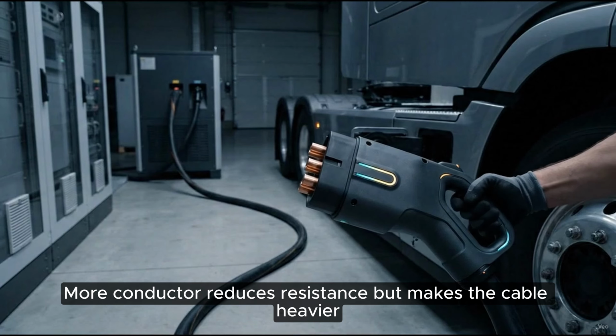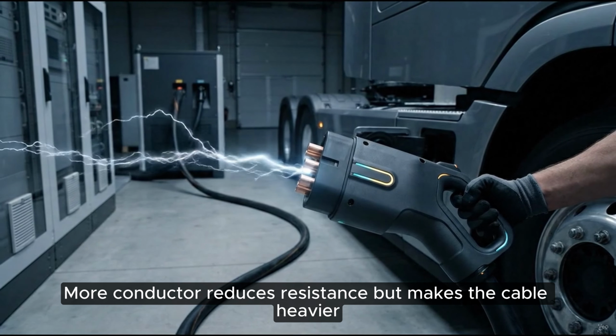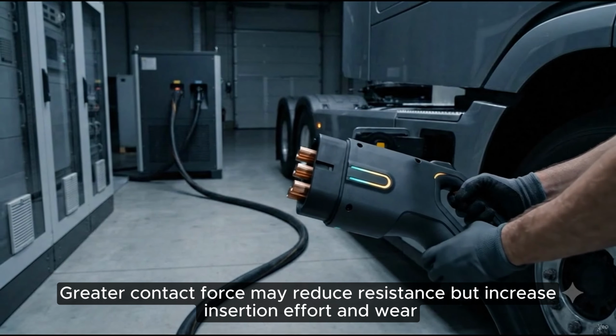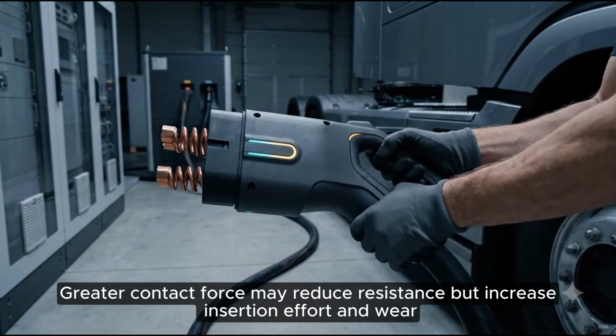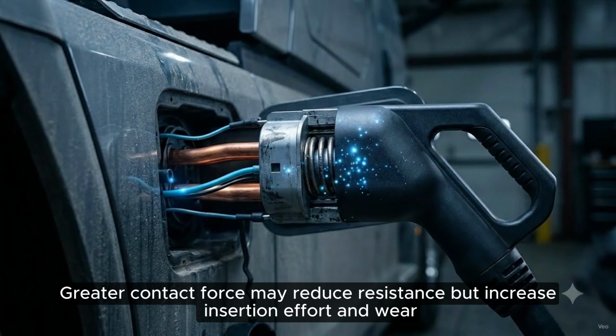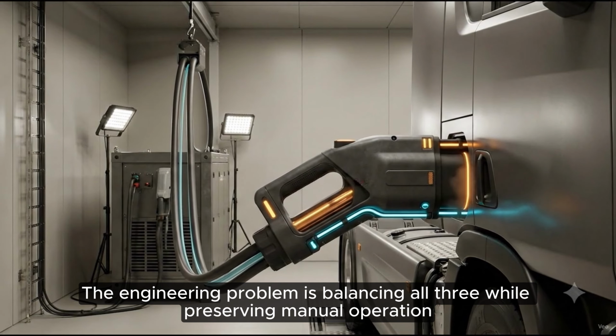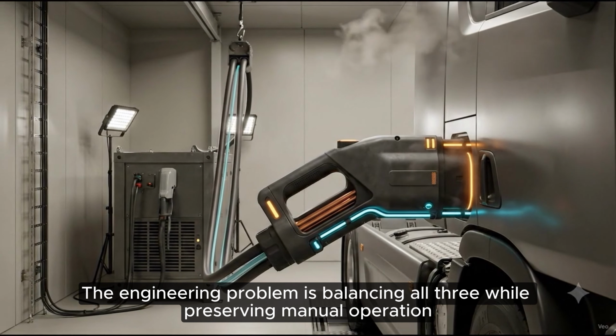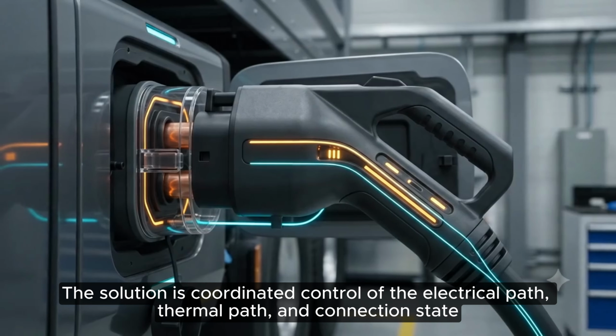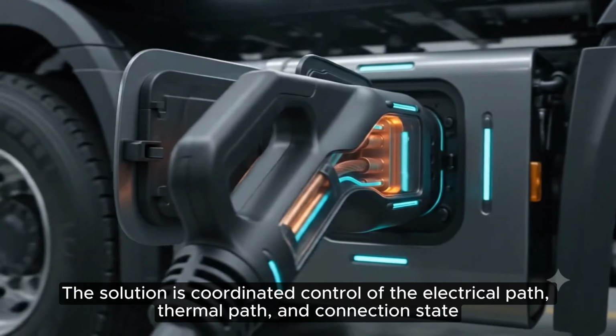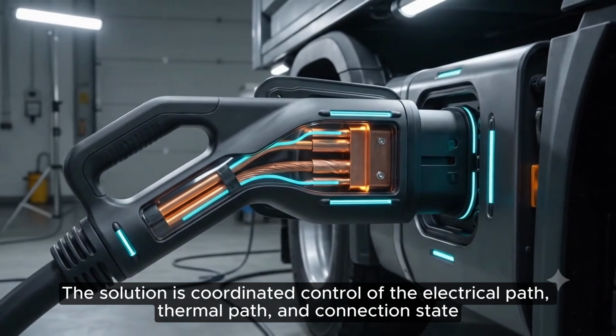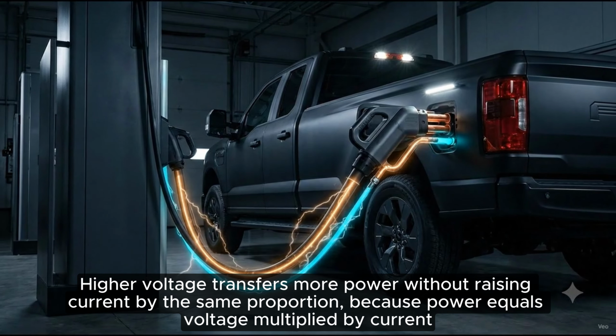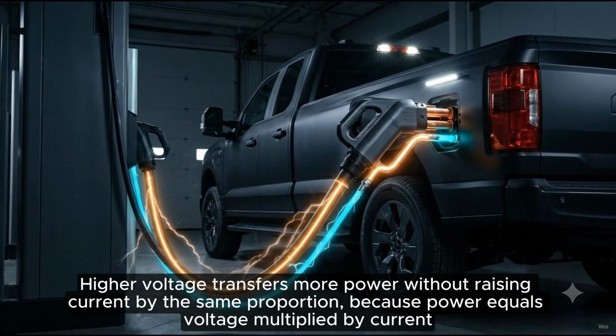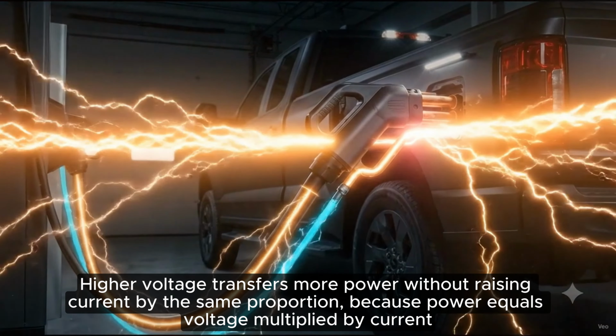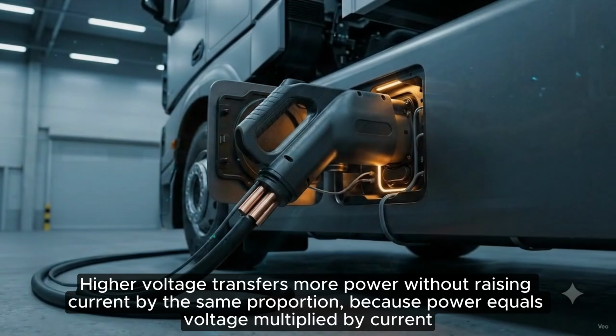More conductor reduces resistance but makes the cable heavier. Greater contact force may reduce resistance but increase insertion effort and wear. The engineering problem is balancing all three, while preserving manual operation. The solution is coordinated control of the electrical path, thermal path, and connection state. Higher voltage transfers more power without raising current by the same proportion, because power equals voltage multiplied by current.